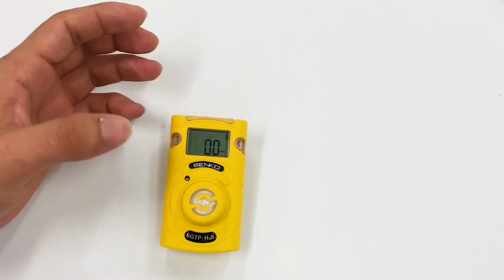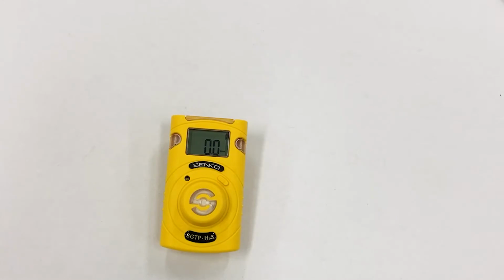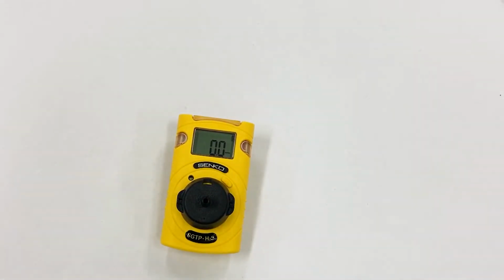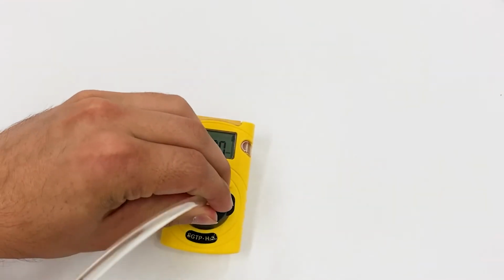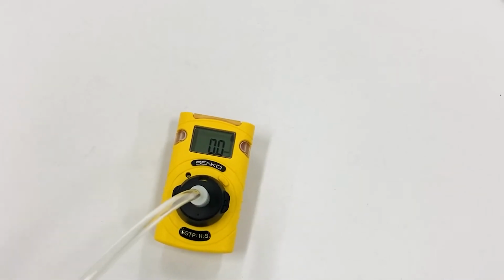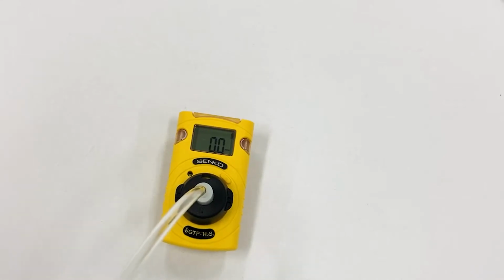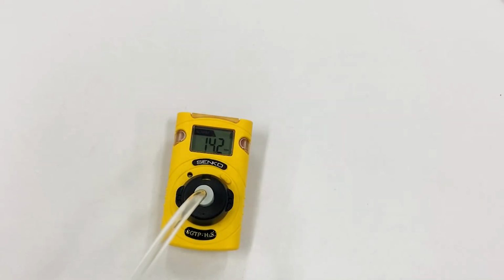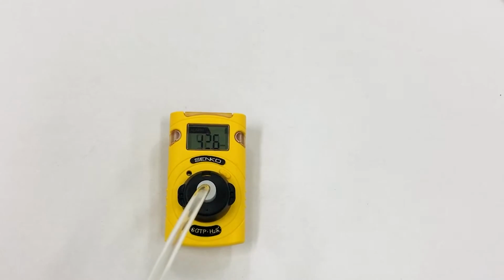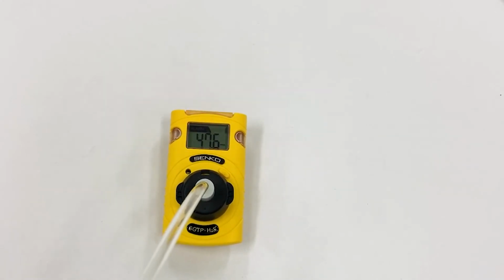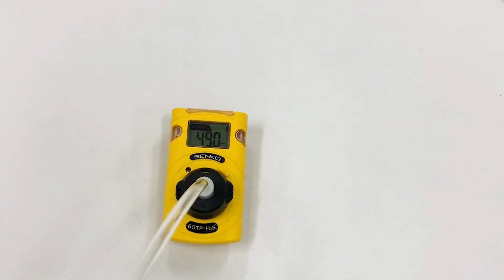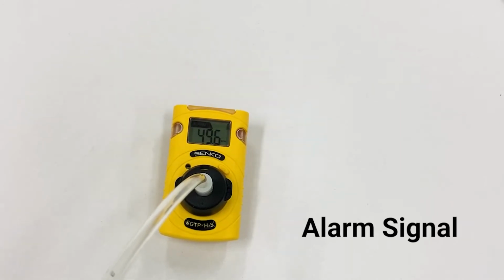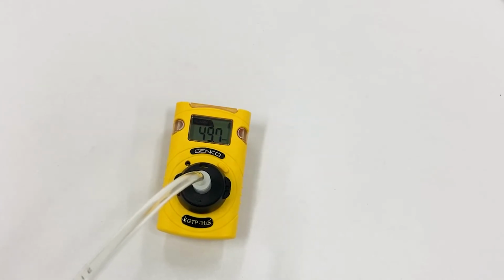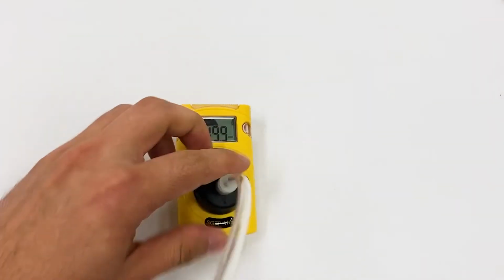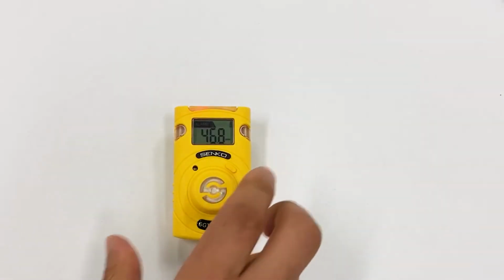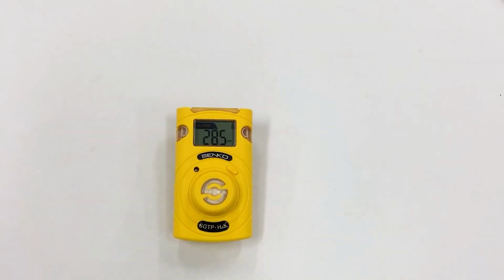So let us demonstrate an alarm by applying some gas using the integrated calibration cap. Opening the gas. By applying some gas on the unit, you can see relatively quick alarms and instantaneous readings of the gas level on the display. Visual alarm, vibration, and audible alarms provide you status notifications. And once we remove the cap, the concentration detected by the device will go down and the device will go back to ambient levels.